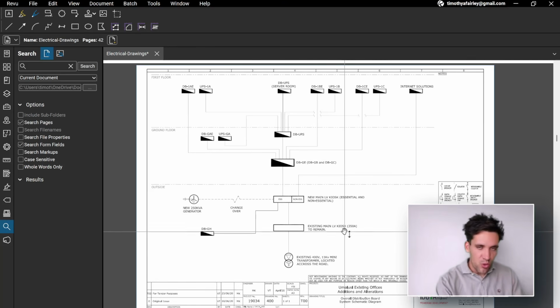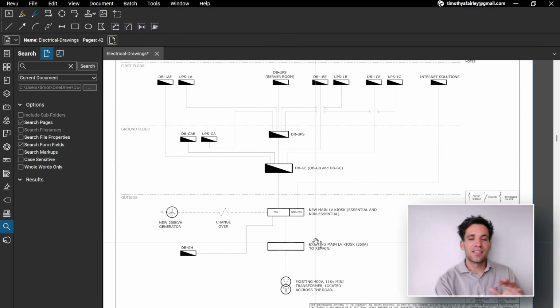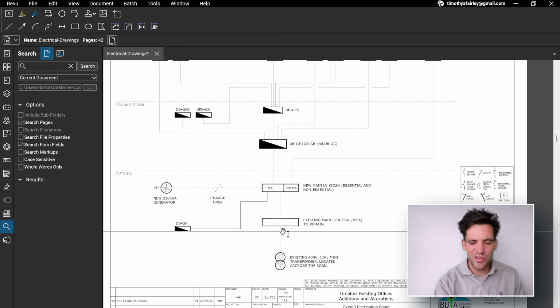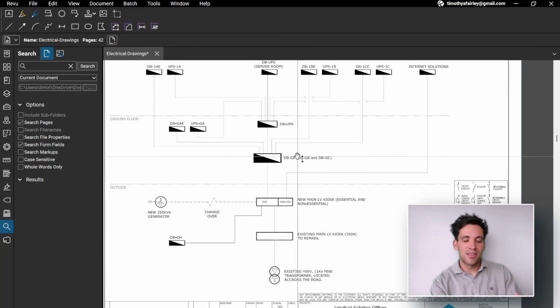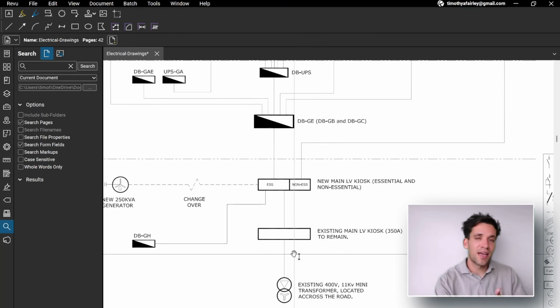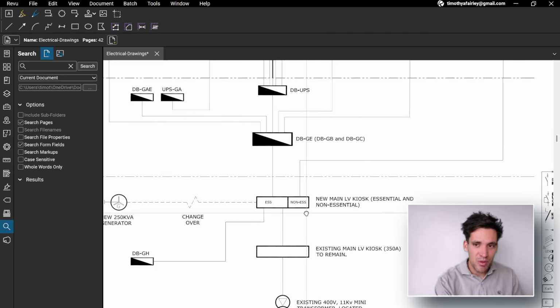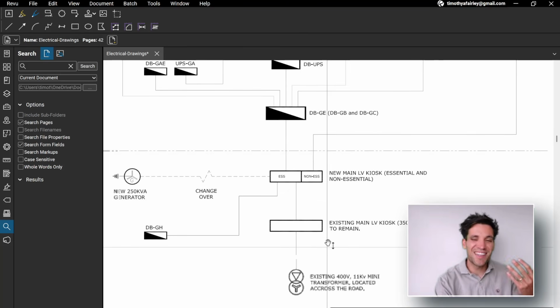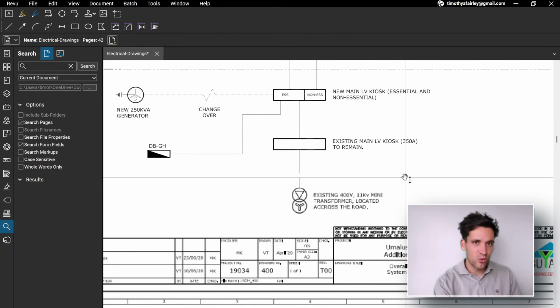So the most important drawing in any electrical design is the single line diagram. Now, single line diagrams refer to the power system. I'll talk about the communications equivalent in a second, but really, the single line diagram shows you the overall power architecture for the system. Each of these symbols represents a specific bit of equipment. The lines between them are the actual cabling that connects them. Well, not necessarily cable. Again, might be bus bar. If you're talking about a substation, it might be something different. But in general, if we're talking about a building, this will be insulated cable that connects all these devices.